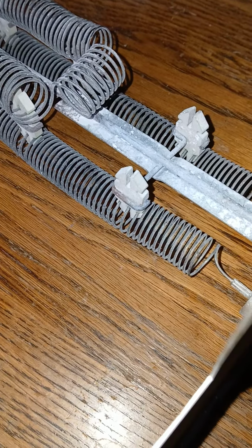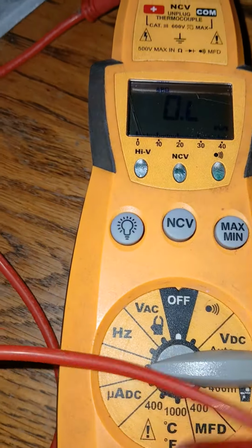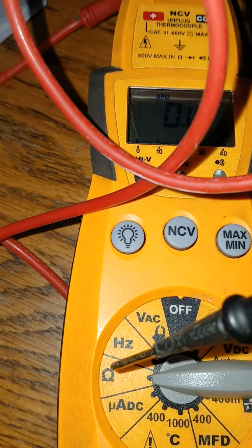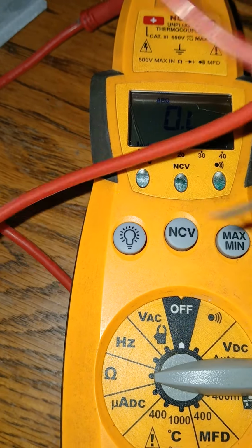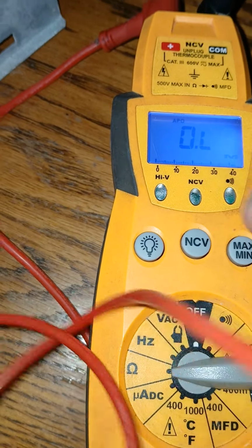Notwithstanding, this is a 5K heat strip. The topic of this conversation is we're going to use an ohm meter. We're going to put it in ohms, which is this little horseshoe symbol on this meter. We'll turn the backlight on so we can see it. Different meters have different configurations. Keep in mind, if this coil were broken, it may read OL.